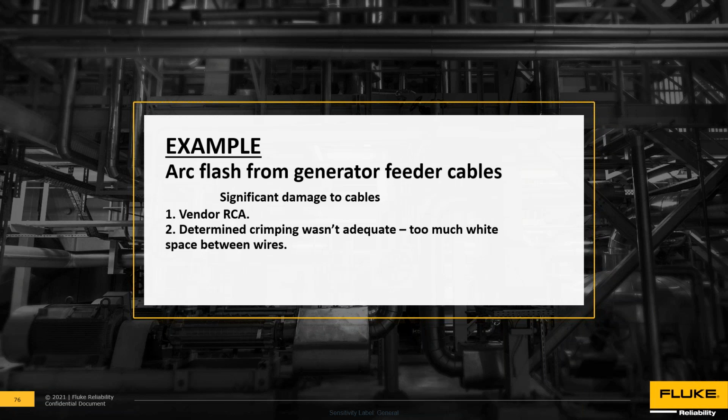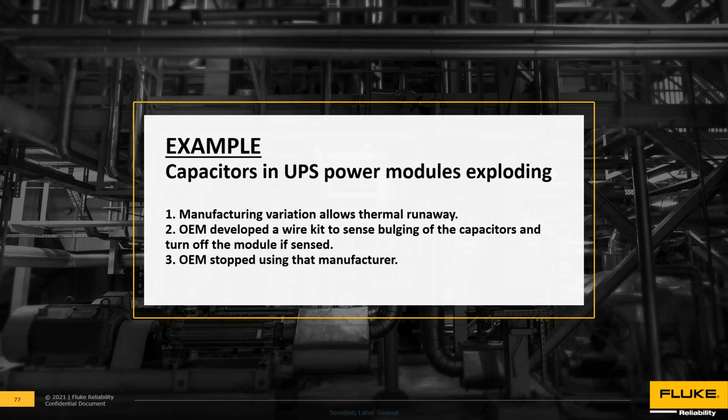Which is kind of interesting. I hadn't really seen that type of a solution for something like that. But this is in one of our UPSs. We had some problems with some capacitors that actually sort of exploded. They caught on fire, shut a bunch of stuff off, and of course you never want to have any kind of a fire.